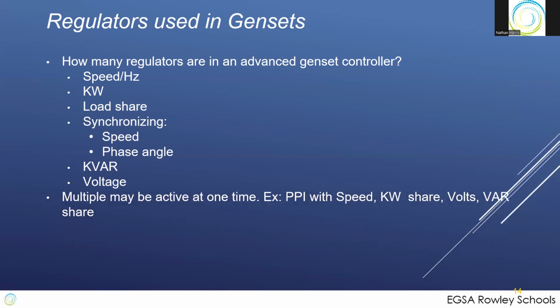Another example is they may be active at one time. So if you have a parallel power island, you could have speed and kW and/or kW share, volts and VAR all active at the same time. And as you know through your power triangle, volts, amps, and watts react with each other. So they can interact with each other through the regulators. If you increase your volts, you might actually increase some watts, even though you didn't adjust your watts, it still might result in an increased watt flow.